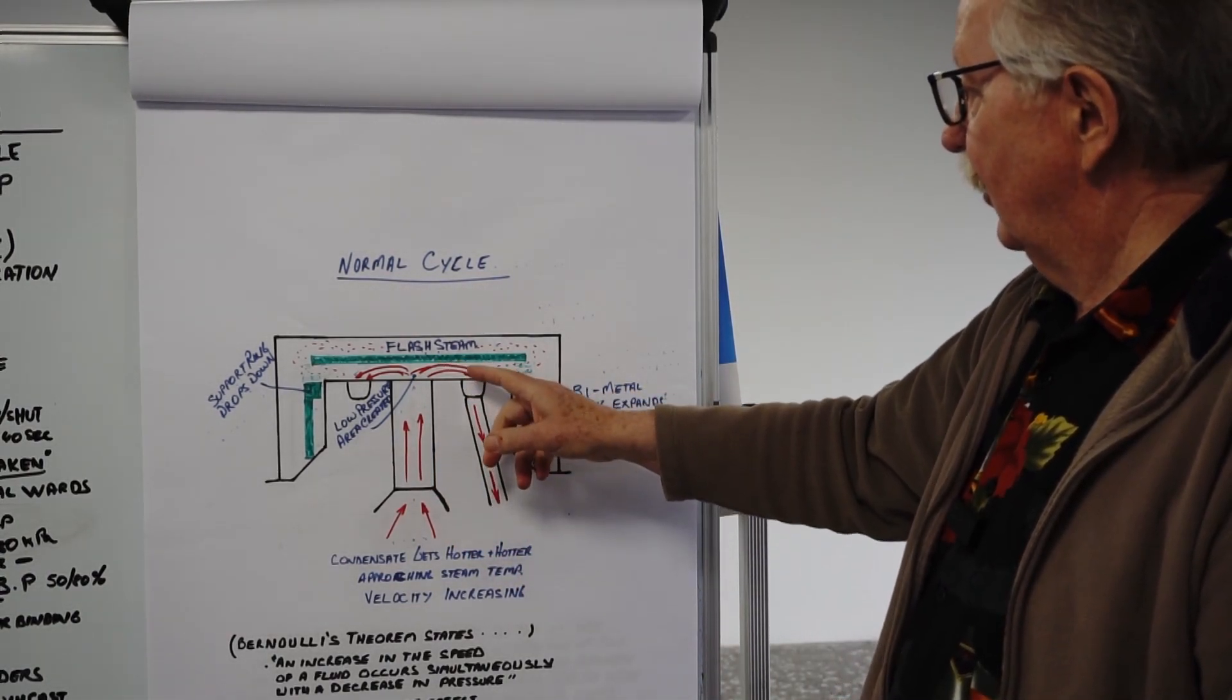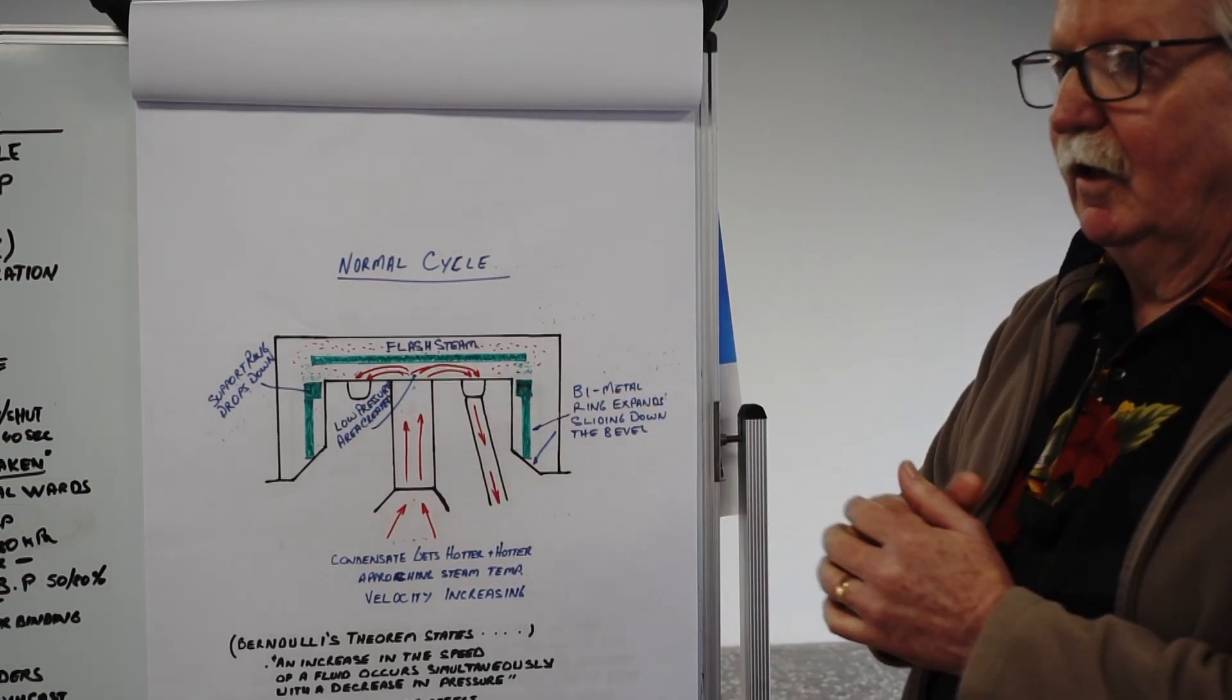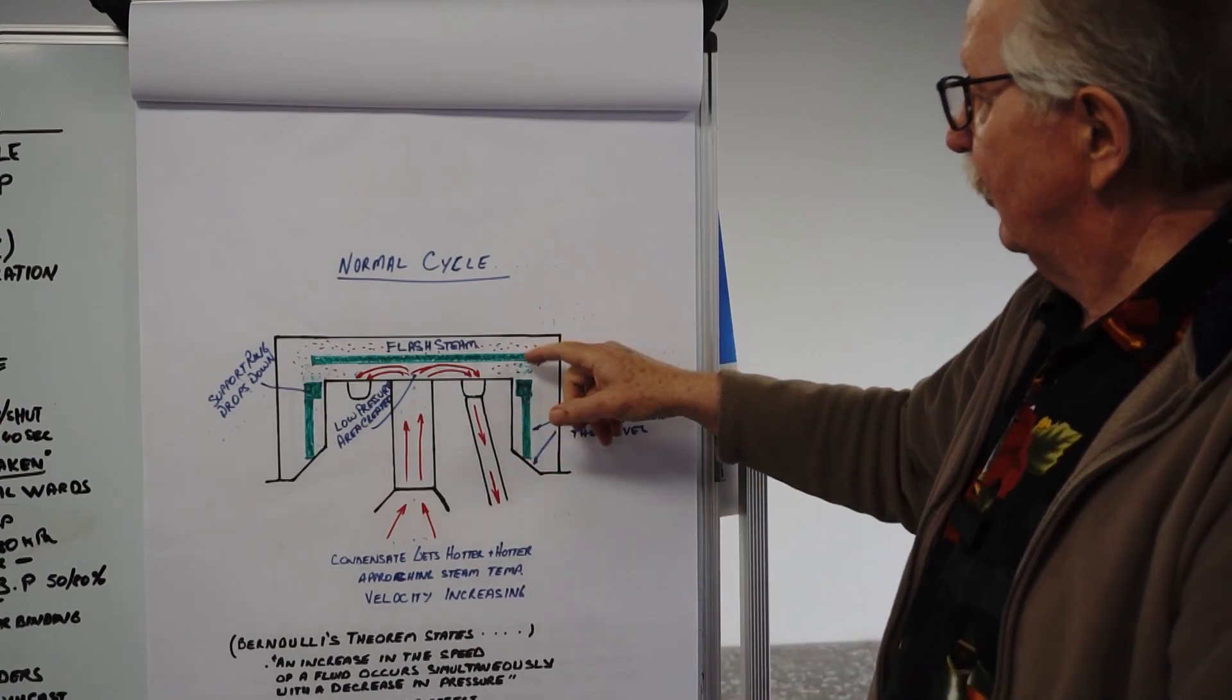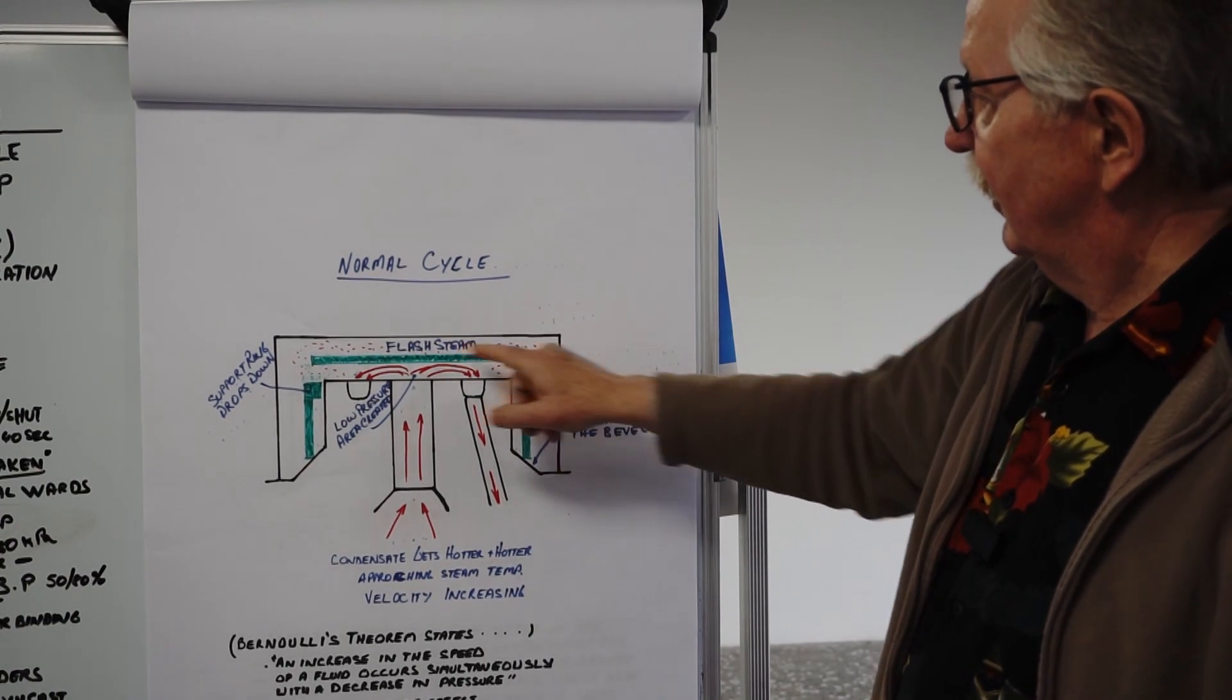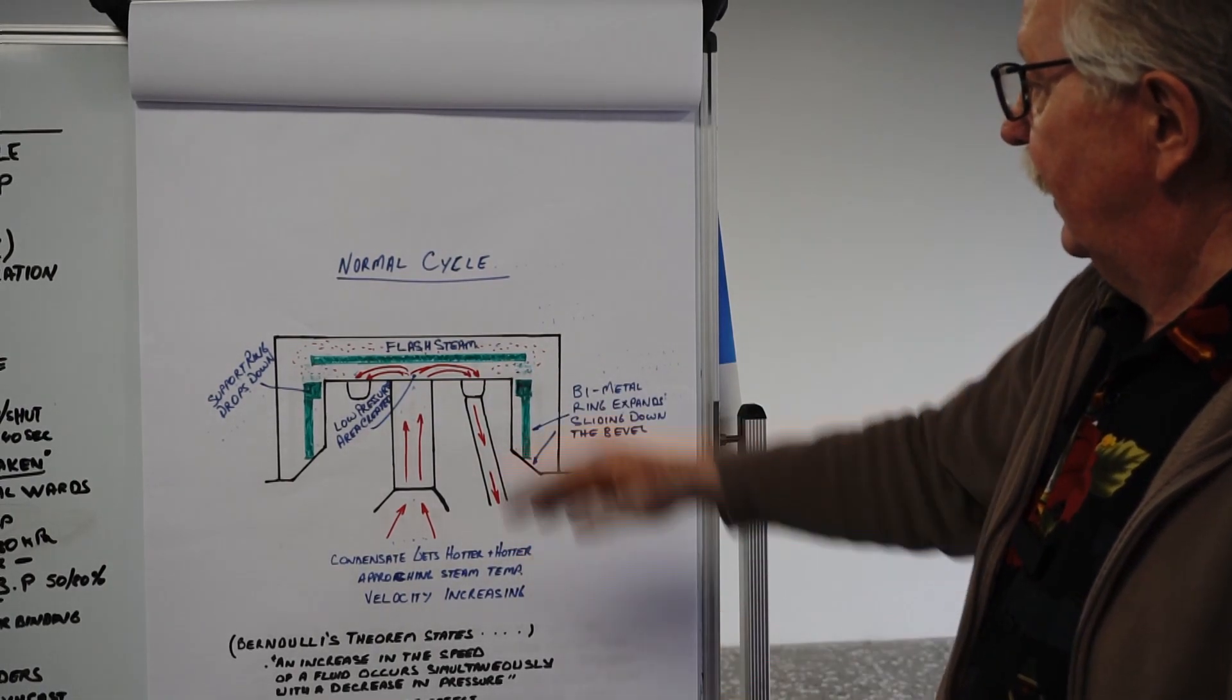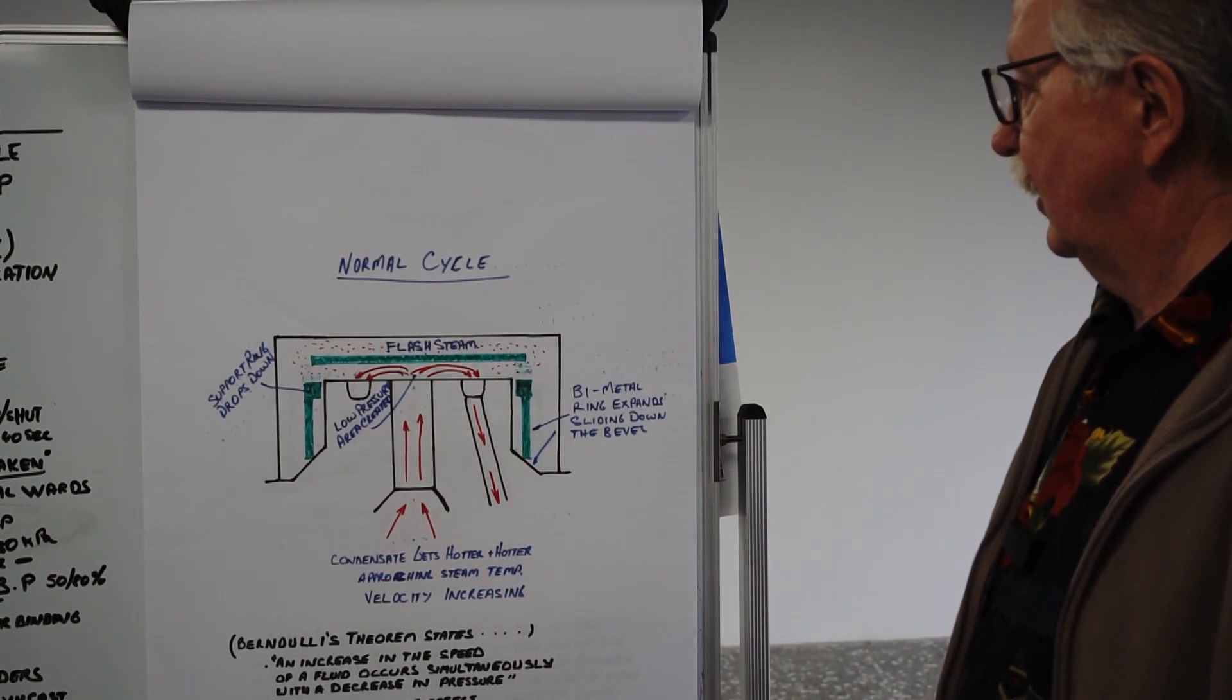When that velocity is fast enough and there's less and less condensate and more steam coming through, the pressure drops here. Any condensate that is in that low pressure area will flash off. So you'll get a certain amount of flash steam that will want to find its way around the disc and up on top of the disc in this control chamber here. As it enters the top of the disc and starts to build up more pressure over the larger surface area there, and that pressure is in excess of what the pressure underneath the disc is, it will snap shut. When it snaps shut, that's your off position and the cycle stops—there'll be no flow through the steam trap.